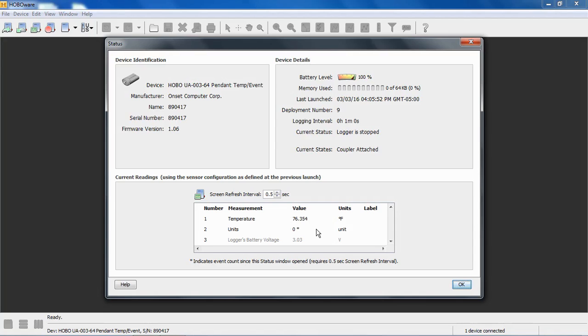The logger events are just a count. You don't get the duration of how long that was closed for. If you think about how a tipping bucket rain gauge works, it's just a temporary switch closure that indicates one tip of the bucket, and that equates to a certain amount of rain or a certain volume of water.